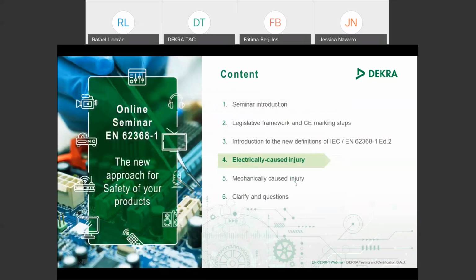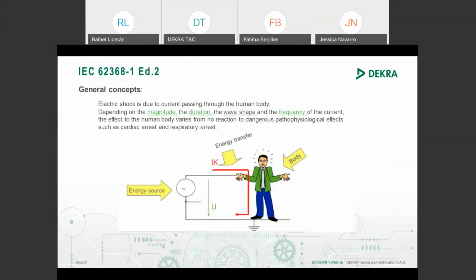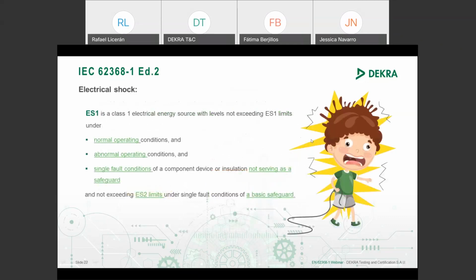Okay, now we begin with the electricity part of the standard, which causes injury. You know, probably better than me, that electric shock is hazardous for people. Then I have to check the magnitude, duration, frequency, and of course the shape of the wave of the electricity that my equipment has. In this way, I have to check the port, the accessibility, the electrical part of the device in ES1, 2, or 3.